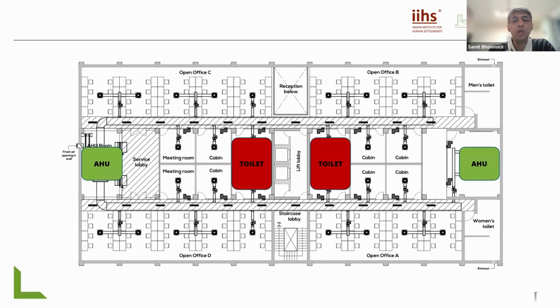Because the toilets don't have any exterior or external wall, we need to exhaust them to the roof of the building. That sounds very attractive, but in my own experience, I've found this to work only in short buildings, maybe 2 or 3 floors. As buildings become taller, it becomes more difficult to extract from the lower floors, and you can see the ducts start becoming longer. When ducts become longer, you also start consuming more energy for doing the same job.